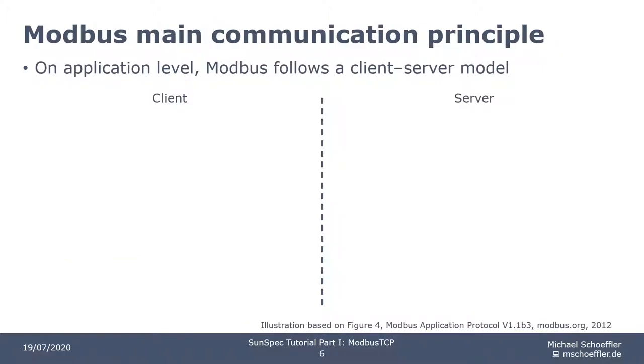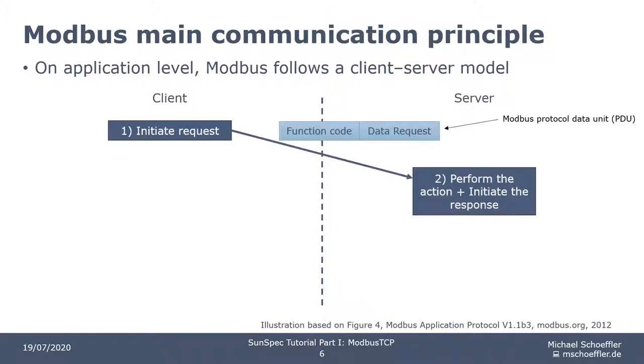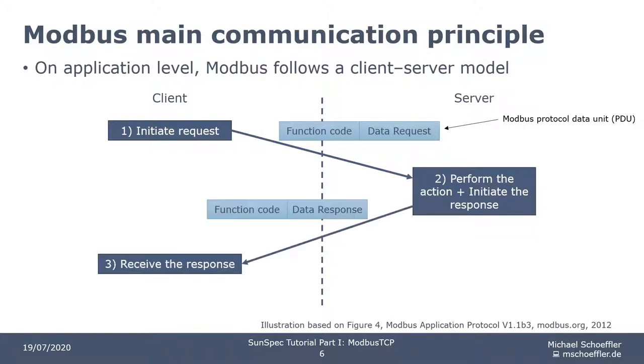What you see here is the main communication principle of Modbus on the application layer. Modbus follows a client-server model. The client initiates a request and sends a so-called Modbus Protocol Data Unit (PDU) to the server. The PDU consists of a function code field and a data request field. The server receives the PDU and then performs some action, for example changing or returning some data. The response is sent back to the client as a PDU with a function code field and a data response field.